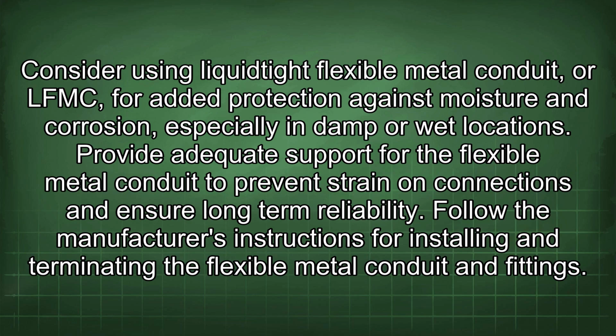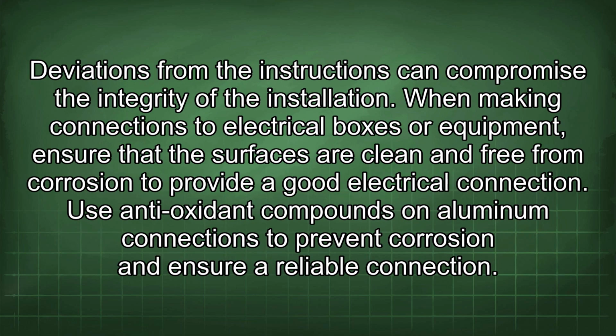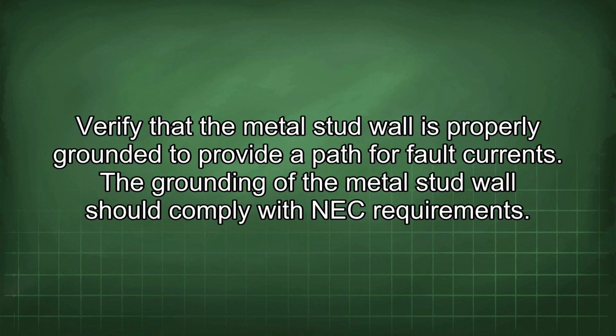Follow the manufacturer's instructions for installing and terminating the flexible metal conduit and fittings. Deviations from the instructions can compromise the integrity of the installation. When making connections to electrical boxes or equipment, ensure that the surfaces are clean and free from corrosion to provide a good electrical connection. Use antioxidant compounds on aluminum connections to prevent corrosion and ensure a reliable connection. Verify that the metal stud wall is properly grounded to provide a path for fault currents. The grounding of the metal stud wall should comply with NEC requirements.